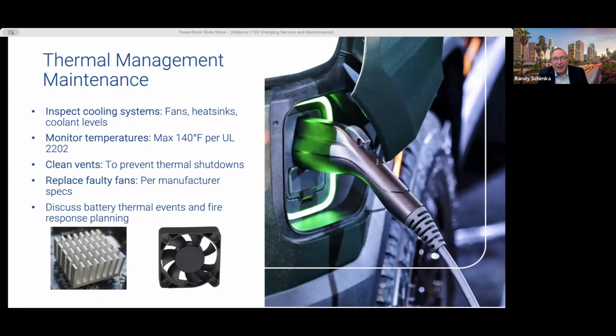Next, take a look at the temperature inside the charging station. The goal is to keep charger components below 140 degrees Fahrenheit per Underwriters Laboratories UL 2202 standards. You can use thermal sensors or cameras or diagnostic tools to catch any hot spots before they can cause issues. For cleaning vents, remove dust and debris to ensure proper airflow with a vacuum or with compressed air. Clogged vents can trigger thermal shutdowns, so routine cleaning is critical for maintaining uptime. When it comes to replacing faulty fans, follow manufacturer specs and use compatible high quality parts. Swapping out failing fans promptly helps keep cooling systems effective and chargers running smoothly.